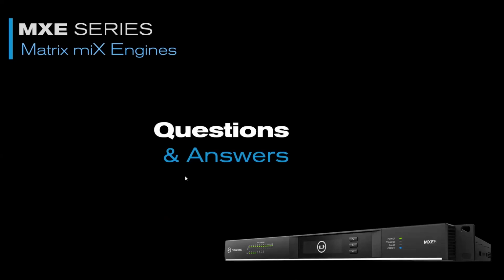The Praesensa or EVAC system, let's assume Praesensa, will be the master, so to say. If there is the EVAC case, and only that is relevant for the EN54, then the MXE5 will be bypassed and not interfere with the EVAC system. So it will be combined, but it won't be part of the certification. It plays very nicely with Praesensa in that system for non-critical functions. When I say critical, I mean the emergency event itself. When the emergency event gets triggered by the Praesensa controller, it will divert away from the MXE and take over full running of the system. So the MXE is capable of being within that system for its normal everyday application, but when the critical event occurs, the system doesn't need to be certified because the MXE is not part of that evacuation system at that point.